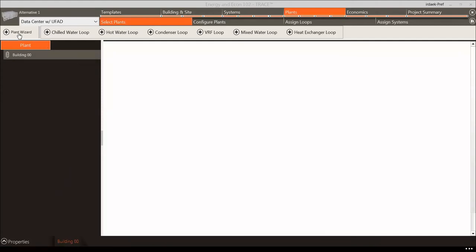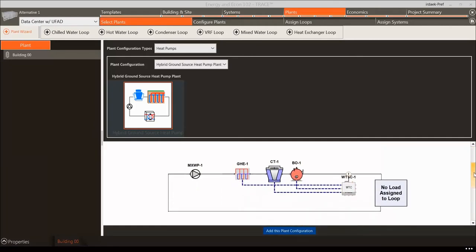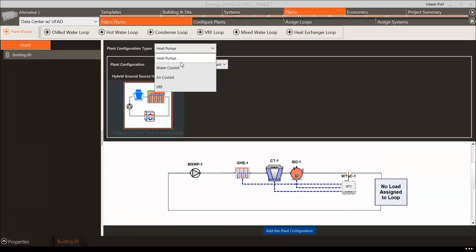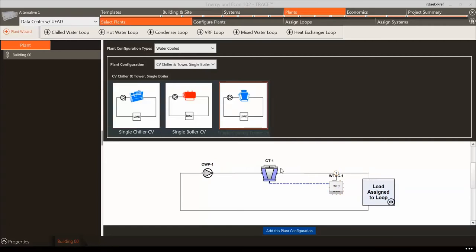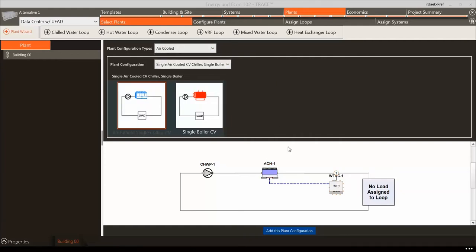Let's use the Plant Wizard to define the plants for our example. Click the Plant Wizard button in the top left-hand corner of the Select Plants tab. Note the Plant Configuration Types drop-down filter, which features heat pumps, water cooled, air cooled, and VRF configurations. Plant configurations are combinations of loops from the loops library with supply and demand connections already established. We need to select an air-cooled chiller for the chilled water coils and a boiler for the heating coils. Click on the single air-cooled constant volume chiller, single boiler, and click Add this Plant Configuration.